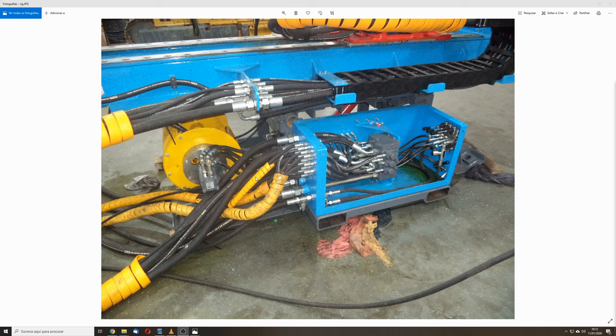A lot of sources recommend checking and setting the load sensing delta P when the pump is standing by. In other words, when it's dead-headed against the closed center of the directional control valve and the load sensing signal line is connected to tank. And this is fine and okay for many systems and pumps, but not all.